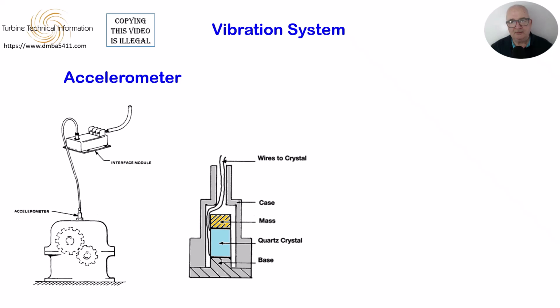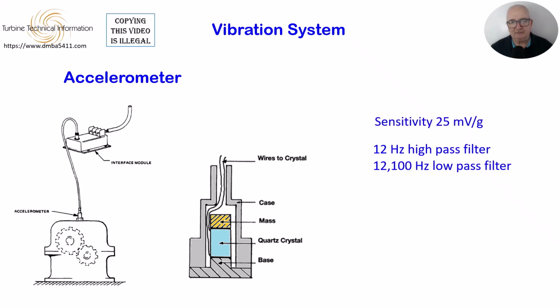Accelerometers use an interface module to power the sensor and process the signal. Typically, the sensor will have a sensitivity of 25 millivolts per G and have a high-pass filter of 12 Hz and a low-pass filter of 12,100 Hz. The alarm will normally be set to 20 Gs RMS and shut down at 30 Gs RMS.